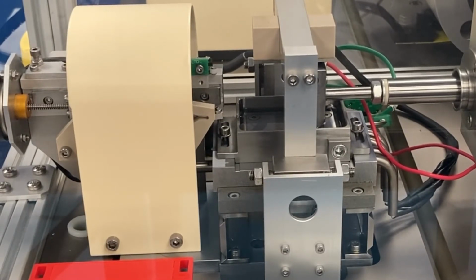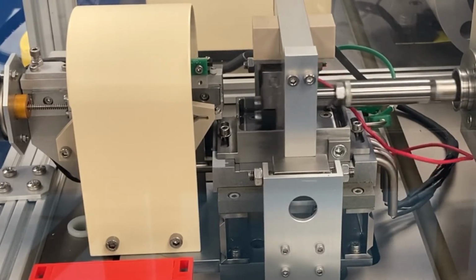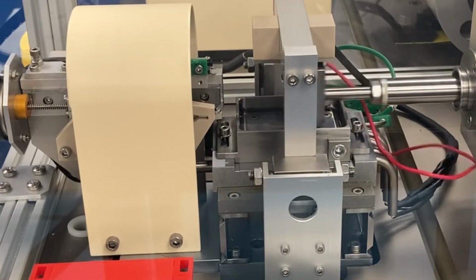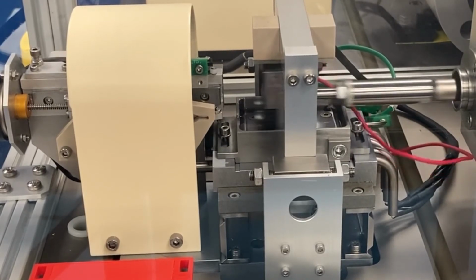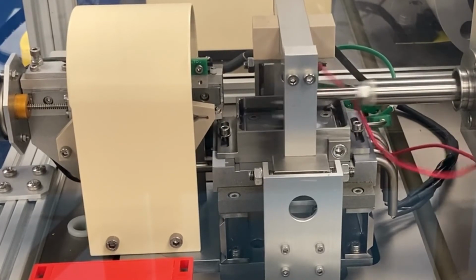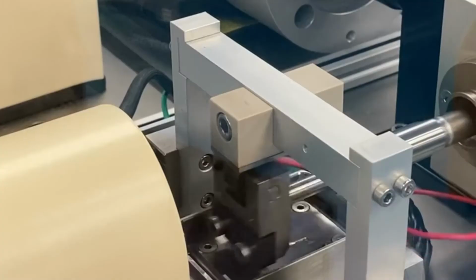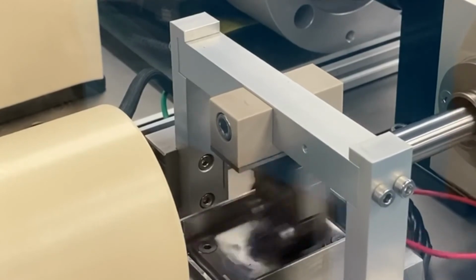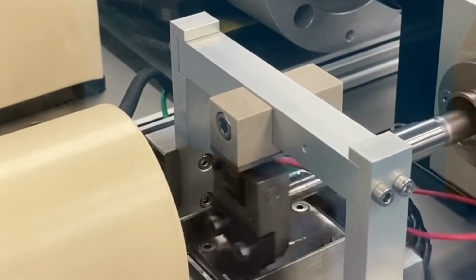As the reciprocating head has to be withdrawn to the opposite end of the specimen to the profilometer, the recommended procedure is to reduce the test load to a low value, say 50 newtons, before withdrawing and parking the reciprocating head, leaving that load applied during the subsequent profile measurement.